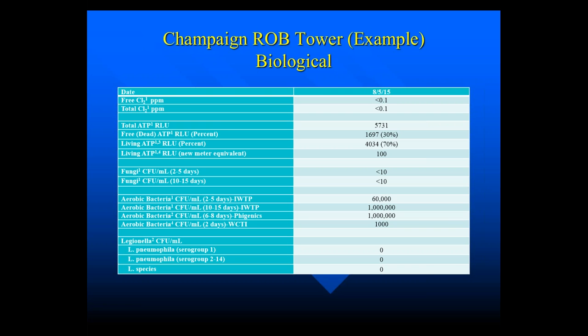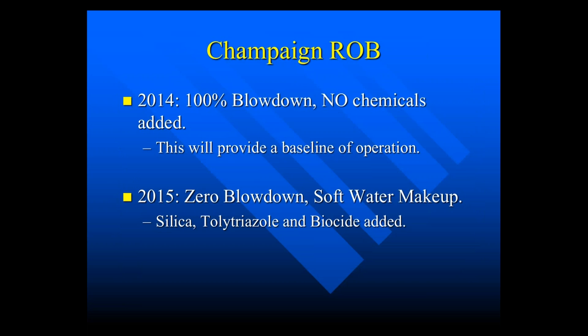Phigenics tested samples after six to eight days, while WCTI tested their bacteria after two days. Phigenics also did Legionella testing. In 2014, we went with the traditional treatment they were using, which was no treatment at all — 100% blowdown, no chemicals added — and that's our baseline.